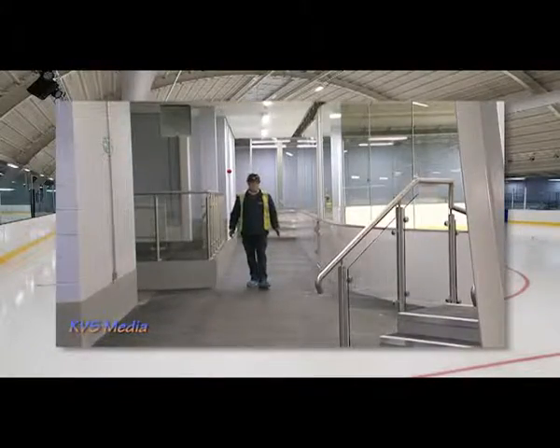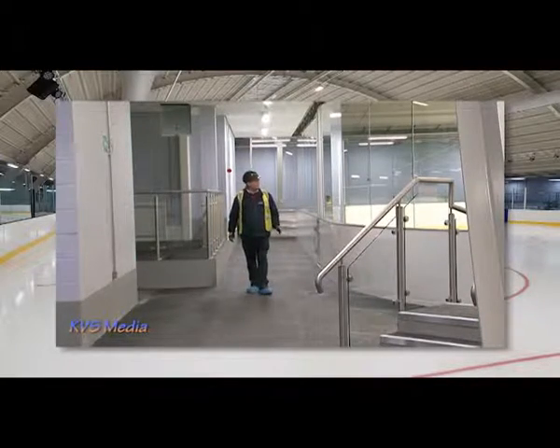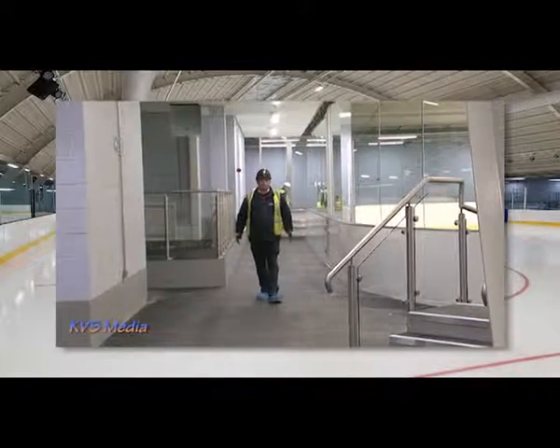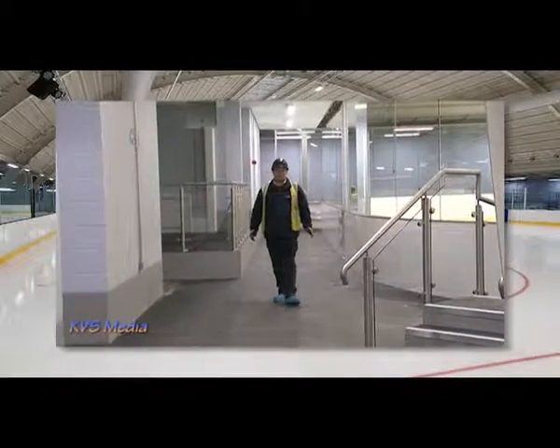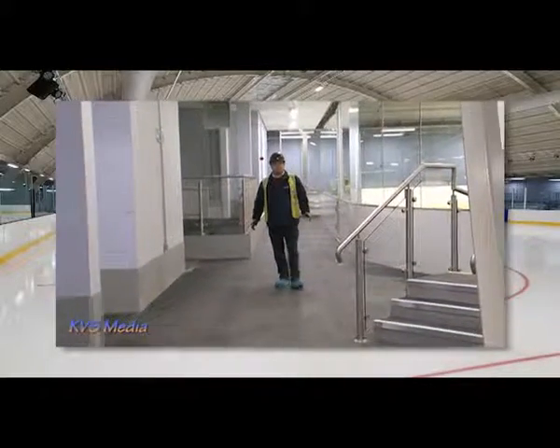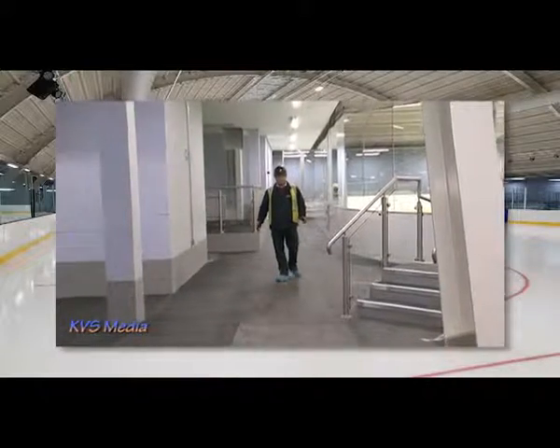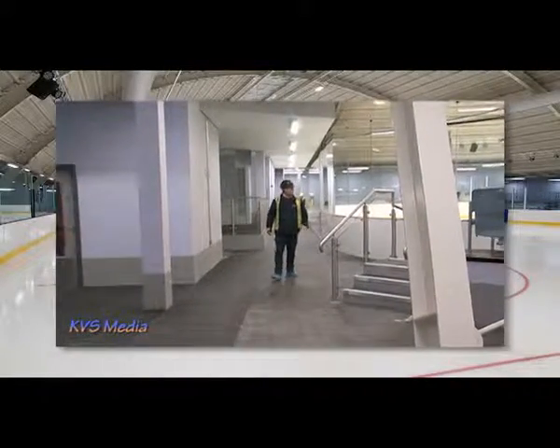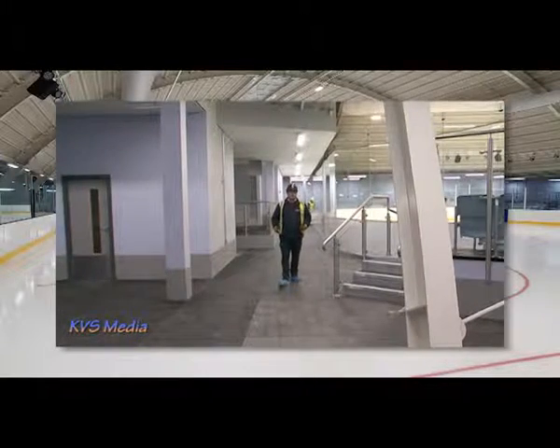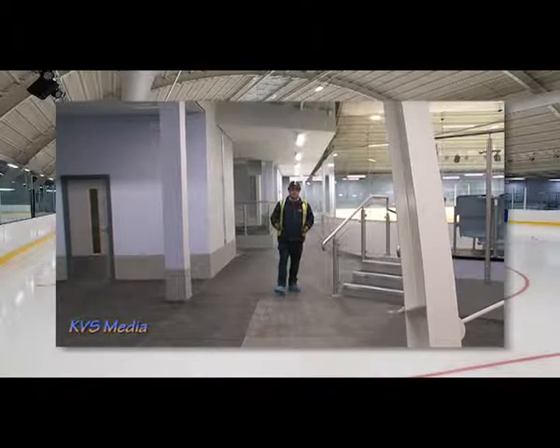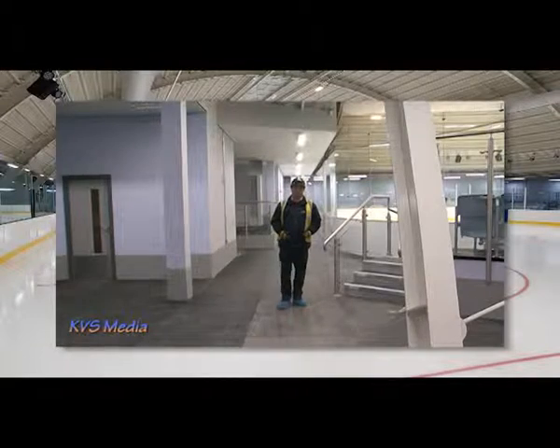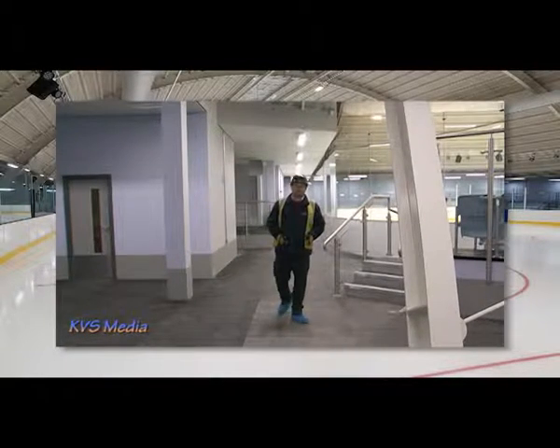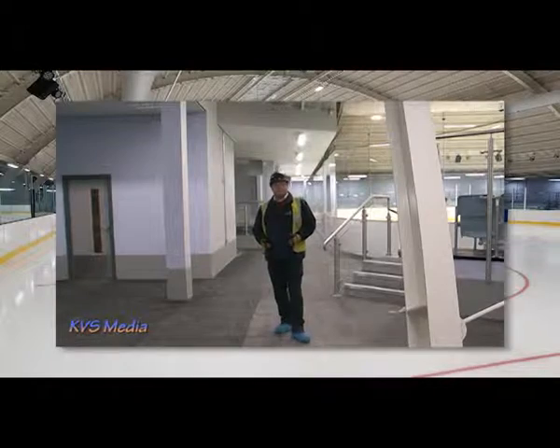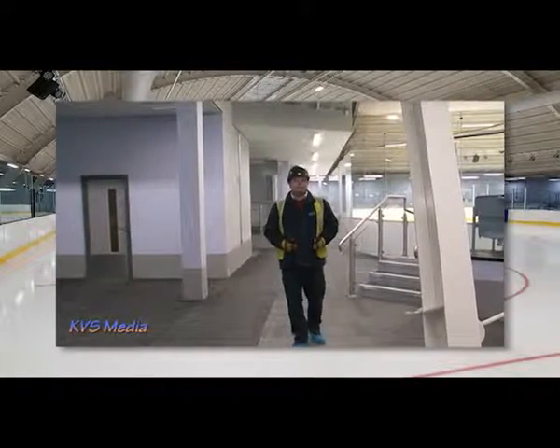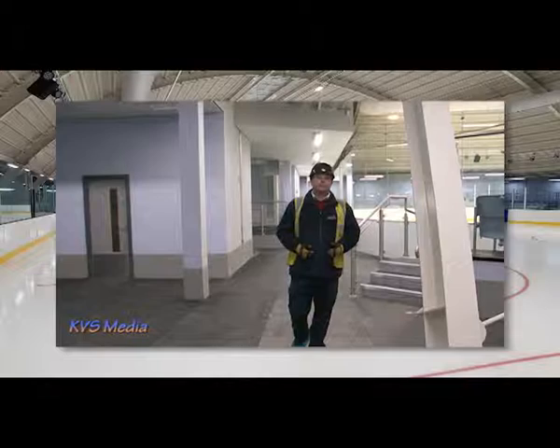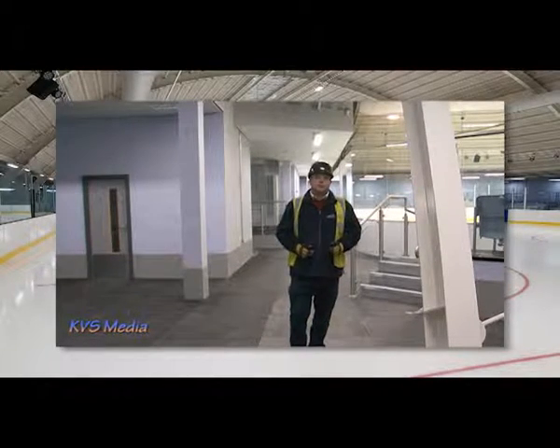We're now down at the south end of the ice rink pad itself, and I'm currently walking over the top of the header trench which houses all of the cold glycol pipes that run underneath the ice. The pipes come to the edge of the pad, and after that there is clear access for GRP panels to be lifted and safe access to be made into the header trench. This area is classed as a confined space and does therefore require a trained and qualified team to access.